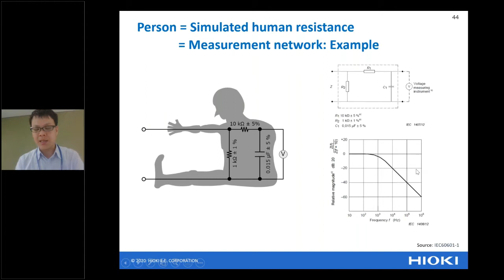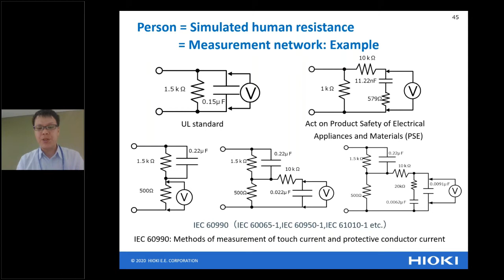So this human circuit is a little different. Each of the standards, the UL standard, mentions these two circuits, and the IEC standard also defines this kind of circuit. It's up to the standard. So for all of the standards, all of the electrical circuits, our product ST5540 has them all. So don't worry. Before measurement, please choose the standard. After that, you can measure like this.